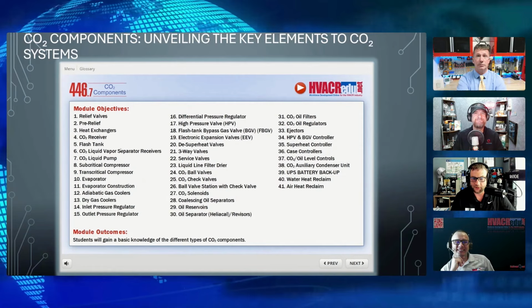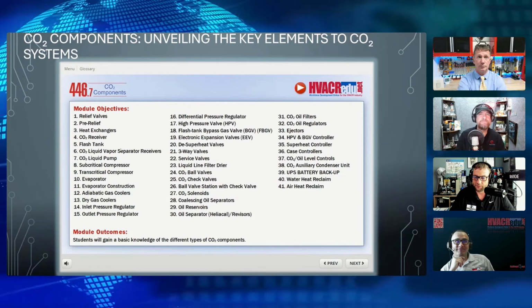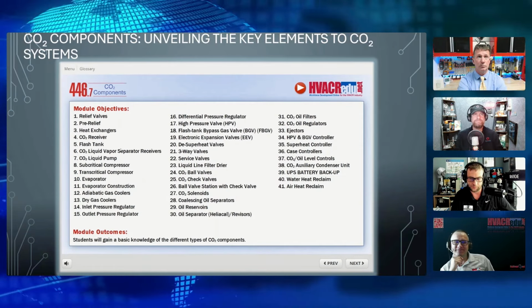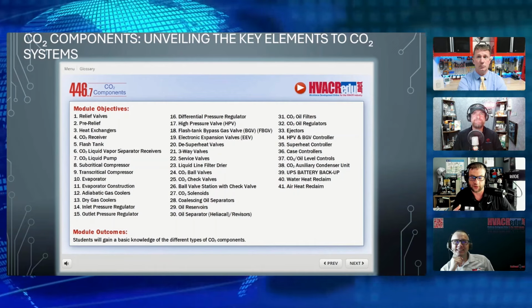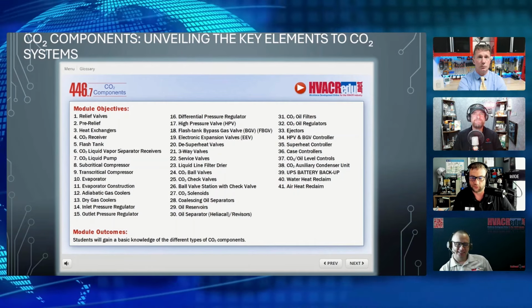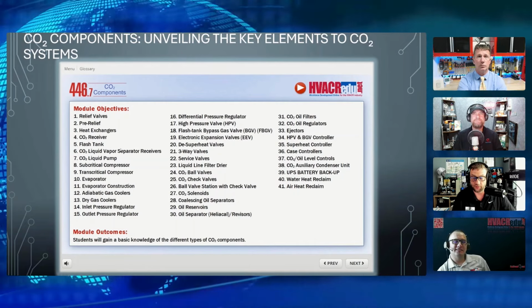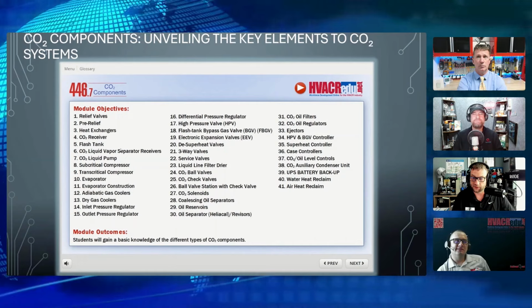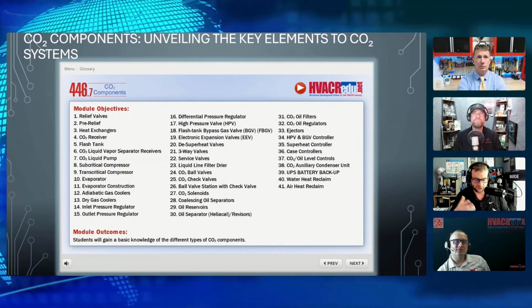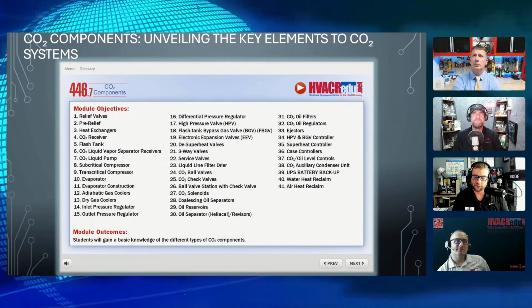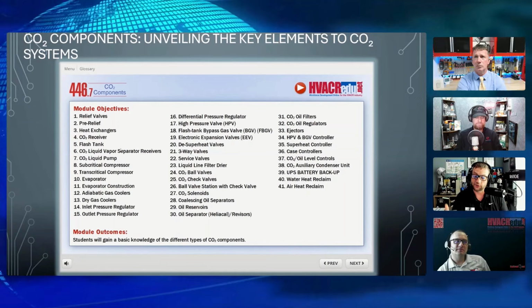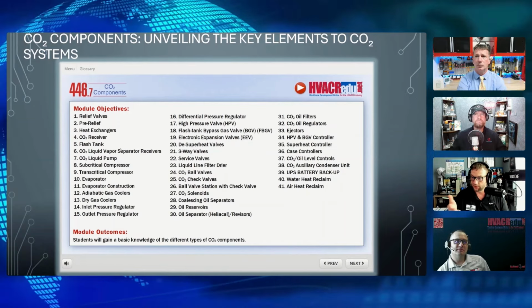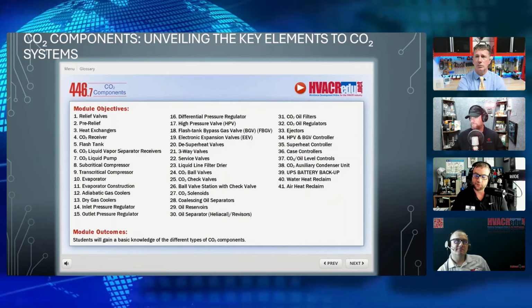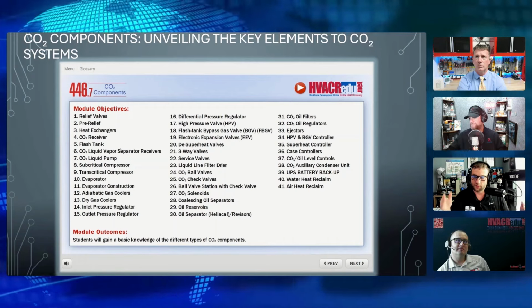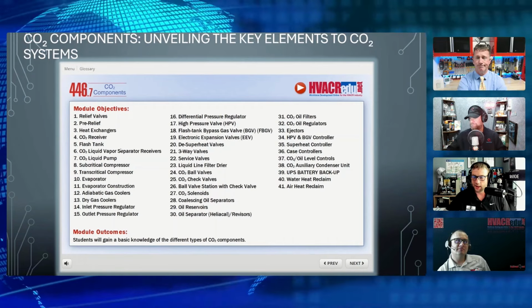I'm like, okay, because we have ball valves, but then we also have CO2 ball valves. And you're like, well, the fact that they can do CO2. No. Some of the ball valves actually have internal check valves with them. Because here's a scenario I'd like to run by you. We talked about the PT chart, the pressure being really obscenely high, right? So, you go to a supermarket, you have an iced up case. What's the procedure? You isolate the system, you pump it out, and you hit it with a hot water hose, right?